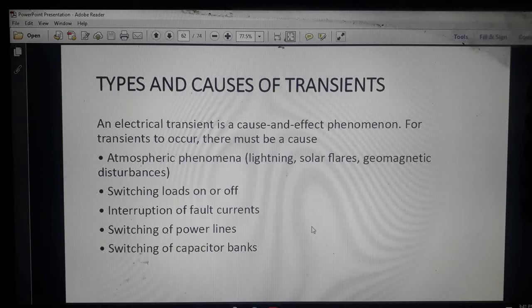Or, if a heavy load is disconnected from our distribution system, an over voltage transient will be generated. Next, switching of the power line. If a power line is connected to the distribution system, it may lead to transient over voltage. And last is switching of the capacitor bank. Sometimes we use a capacitor bank for power factor improvement at the distribution end, which leads to generating transient over voltage.